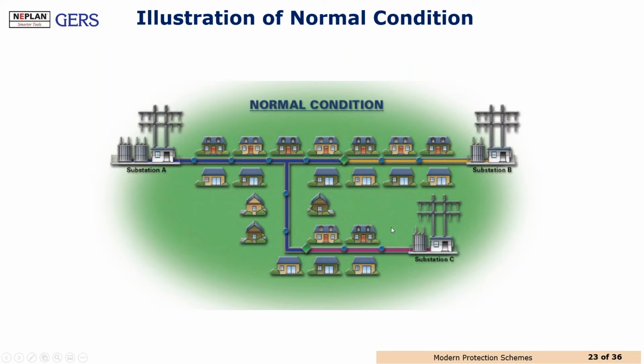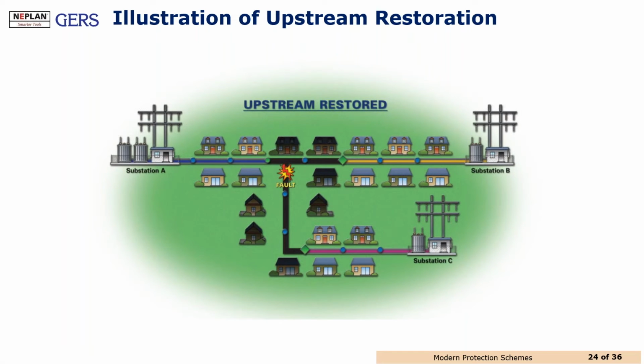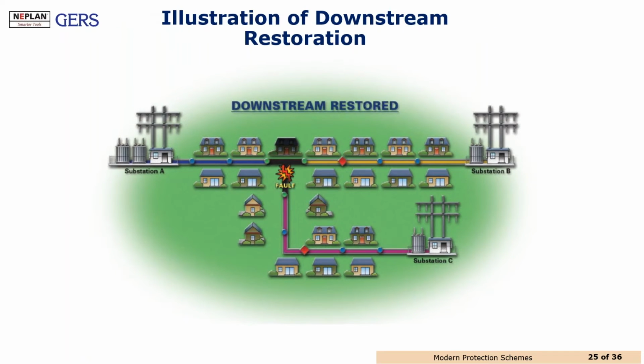In this case, what would happen if any fault occurred? If we have the fault in this location, this breaker will open due to the high current that we have because of the fault. And this breaker and this breaker were initially open. FLISR application means that we can close the other breakers and open the corresponding part of the network, just the part that has the fault. And in that case, we are increasing the reliability since we are able to supply the load for the healthy part of the network.